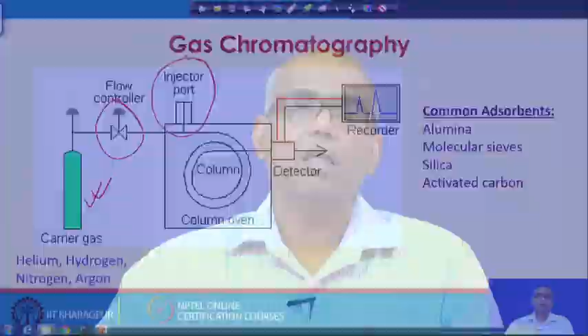Then you have a sample injection system. Now, the sample injection system may be different depending on whether you have a gas sample or a liquid sample. The gas sample injections and the liquid sample injections may take different forms, because when you have a liquid sample, the liquid sample injection will be followed by the vaporization of that liquid. This sample injection may be manual, it may also be automated. In that case it will be a slightly more complex arrangement, but this sample injection system allows you to inject a known specific amount of sample to the carrier gas.